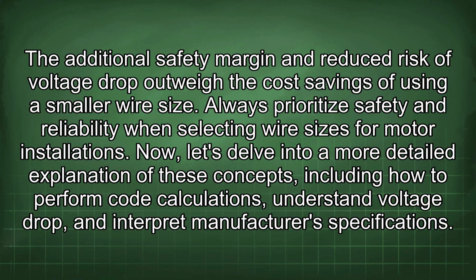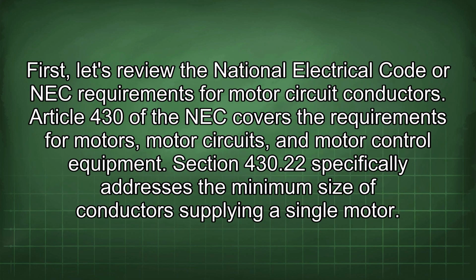Now let's delve into a more detailed explanation of these concepts, including how to perform code calculations, understand voltage drop, and interpret manufacturer specifications. First, let's review the National Electrical Code, or NEC, requirements for motor circuit conductors. Article 430 of the NEC covers the requirements for motors, motor circuits, and motor control equipment. Section 430.22 specifically addresses the minimum size of conductors supplying a single motor.